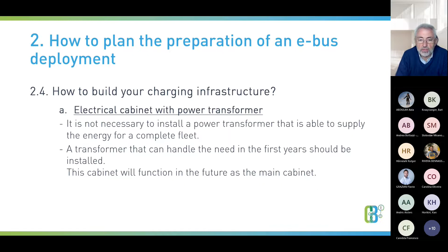First you need a connection to a high power electricity network, with an electric cabinet where a power transformer will be installed. You need cable sized for the maximum future energy transfer, but you don't have to install a transformer able to deliver the full fleet's needs from day one, especially when it takes years to reach that situation. A transformer that can handle the need in the first years should be installed, and this cabinet will later function as the main cabinet.